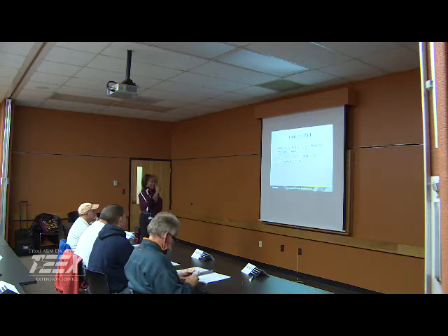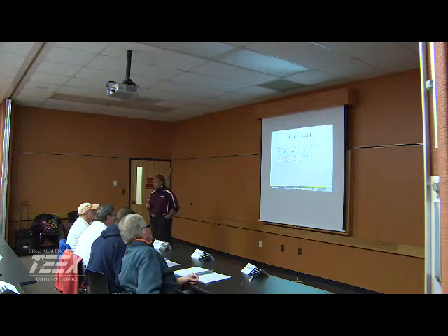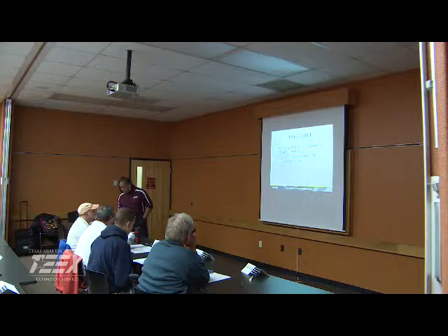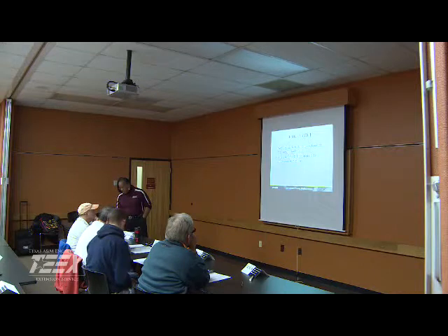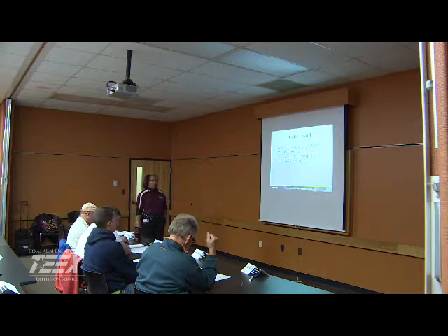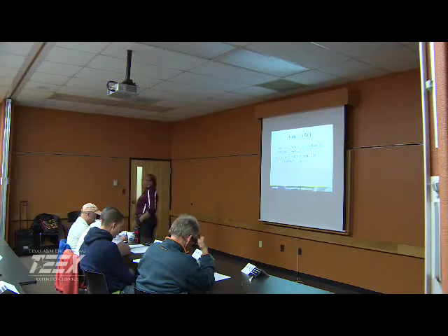So parts of a well: we have the well casing, 6 to 36 inches in diameter, standard weight steel pipe, it can be plastic also. So a lot of different materials can be used for that: carbon steel, high strength low alloyed steel, stainless steel, plastic. You want to make sure that it is conforming at least to the AWWA standards, which is the American Water Works Association.